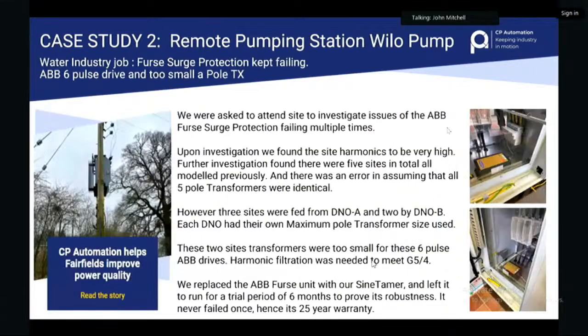This site, again actually a water treatment plant, has a pole transformer, which you see up here, and this site was using ABB Furse surge arresters, which you may be familiar with. Furse have been around for a very long time, then ABB bought them. They were failing roughly once every 3 months on this site, and no one had a clue why. They didn't want to pay for a survey, so we sent them out a SineTamer and said, look, I'm pretty sure it's a problem with how robust the boards are inside the ABB device - you're not going to have this problem with SineTamer.